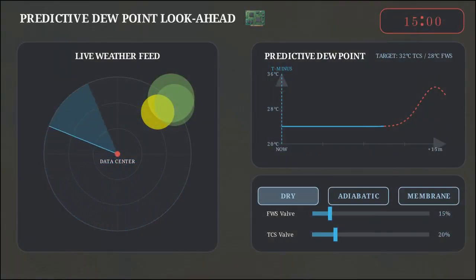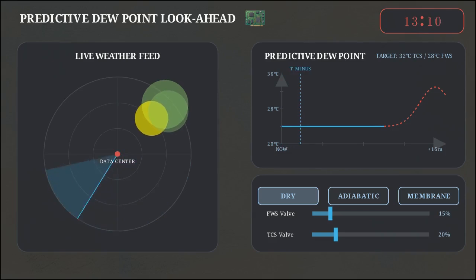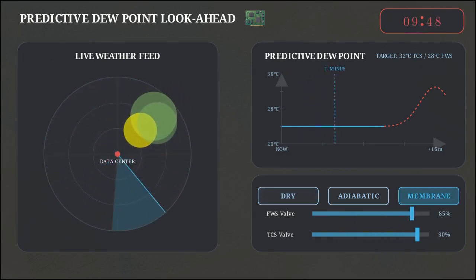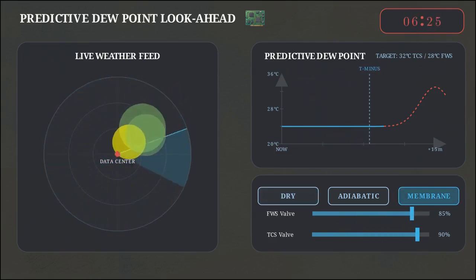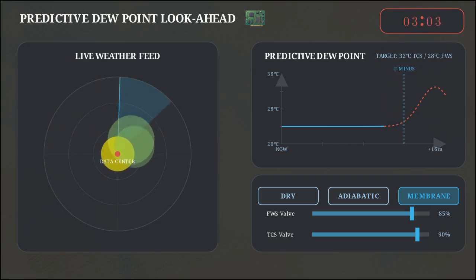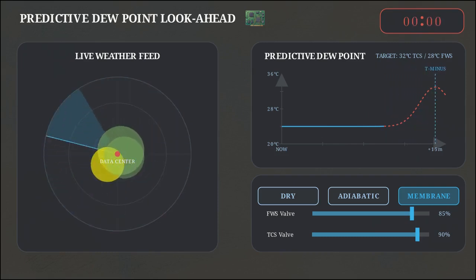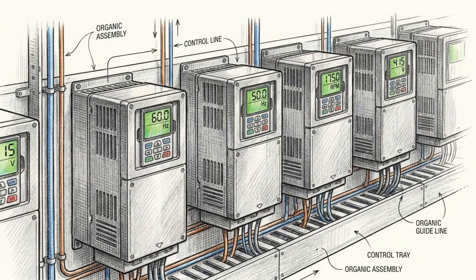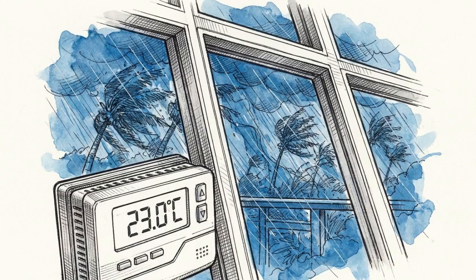System resilience extends to predictive software logic. The plant's programmable logic controllers cross-reference live weather feeds, executing dew-point look-ahead tuning to adjust cooling modes 15 minutes before a high-humidity weather wall arrives. By reacting before the air actually changes, this pre-modulation prevents the fans and pumps from oscillating or hunting for a set point during sudden monsoon or tropical rain spikes.